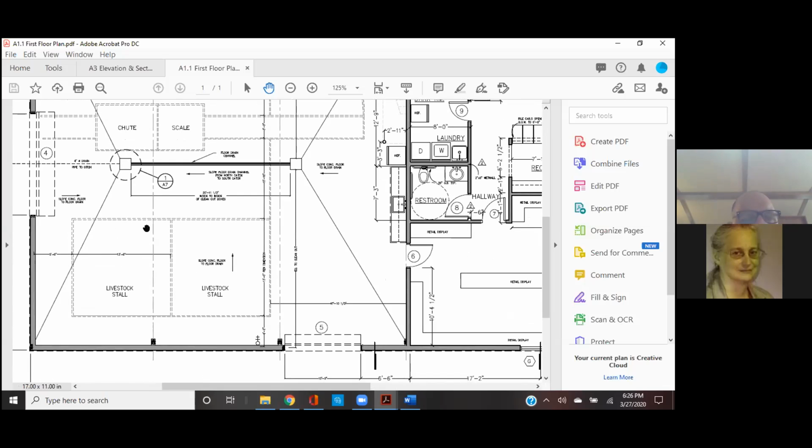And do that 1, 2, 3. Maybe I put an extra one here by the door because you're going to get a lot of air movement through here. You might even talk about putting an air curtain here, so when this door is open, it blows hot air down so that cold air can't rush in. Good thinking. Okay, so that might be an idea. You just put an air curtain there, put 5 in each one of these bays. So 5 vents in each bay. Yes, 5 vents in each bay.